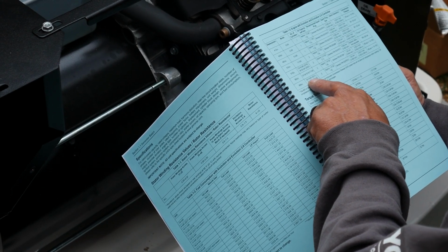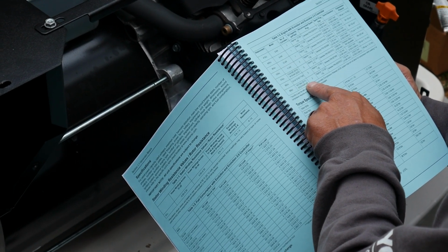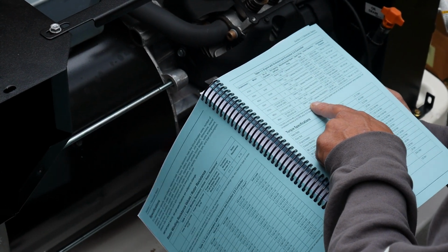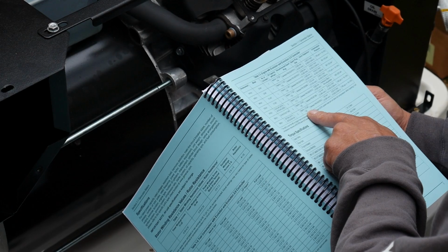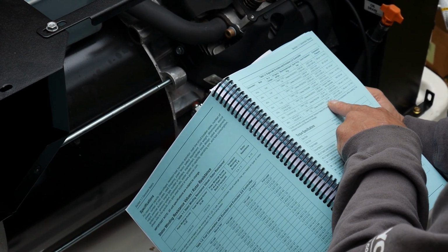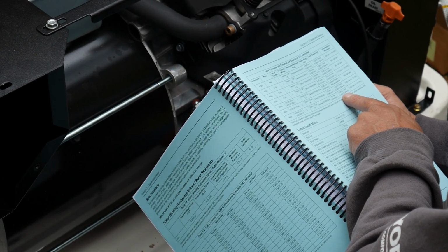Here you find your 999 cc, which is the 16, 17, 20, 22, 24, and 26 kilowatt generator. Number of cylinders 2, approximately 1.9 quarts of oil with the filter change. It gives you the part number for your spark plug, tells you your spark plug gap, and then your valve clearance: 0.002 to 0.004.